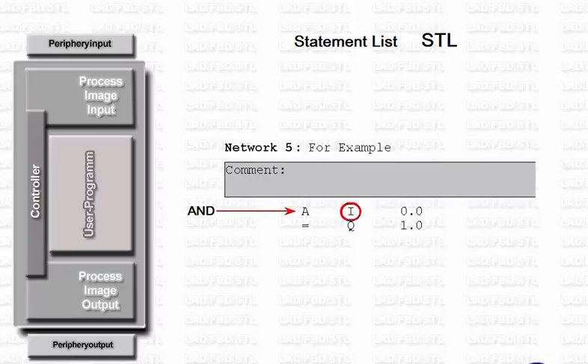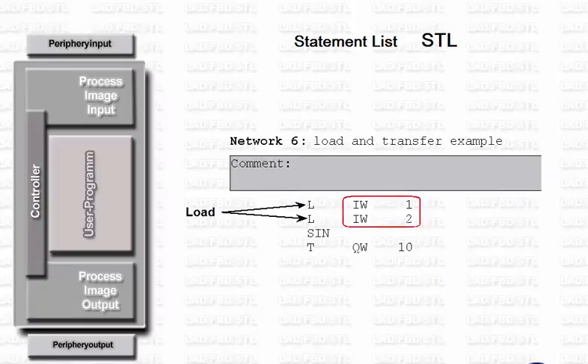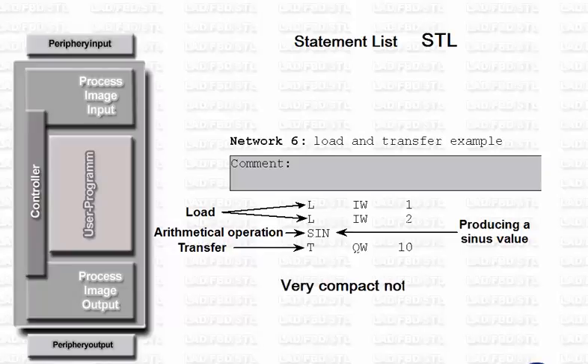Likewise, the operator — for example a process input or output, or a memory bit — is easily interpretable. Digital operations are processed in Statement List by loading digital variables, such as two integers, and combining them, for example by an arithmetical operation. The result is then transferred into memory. The advantage of using Statement List is the very compact notation of the automation task in hand, which saves user memory resources.